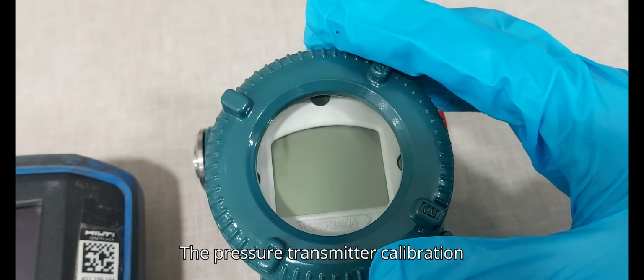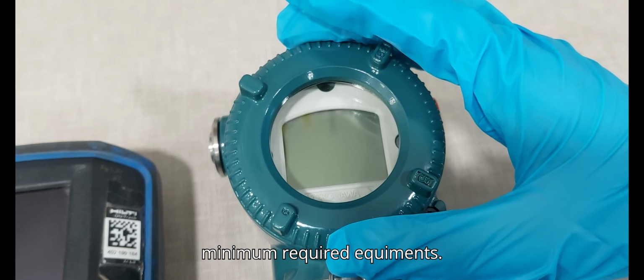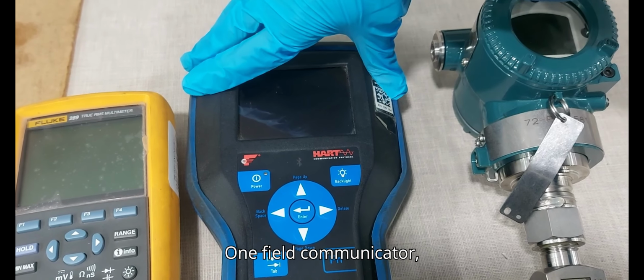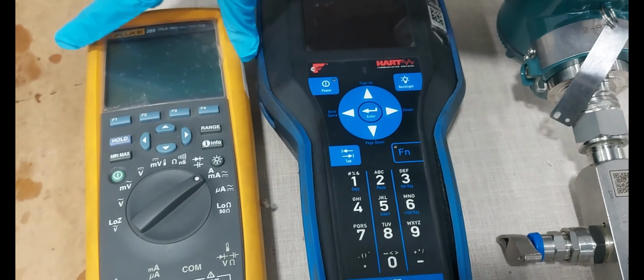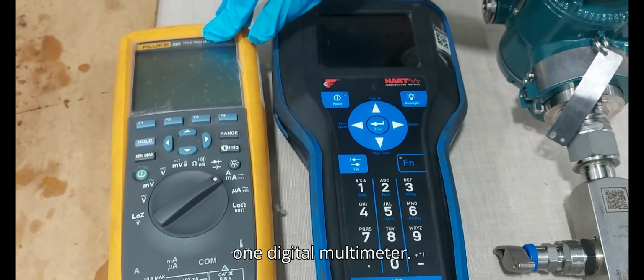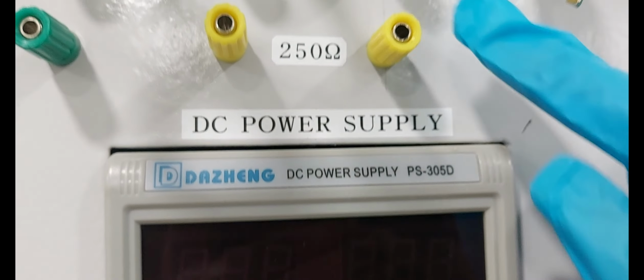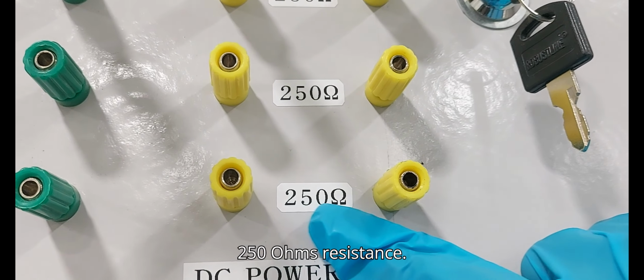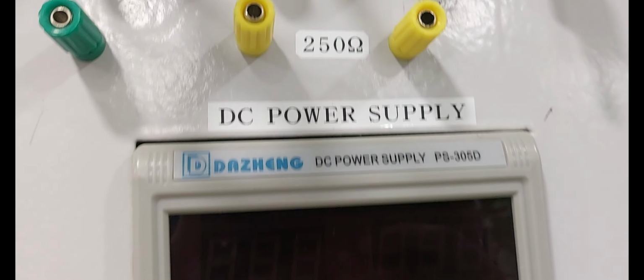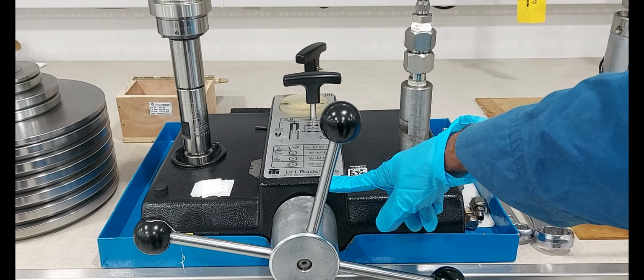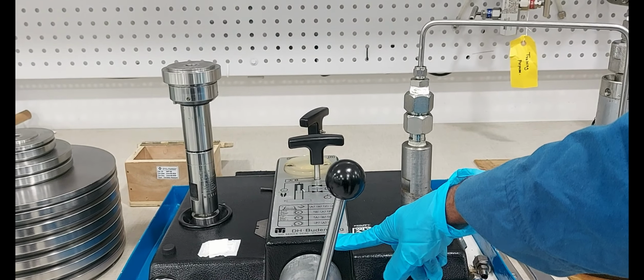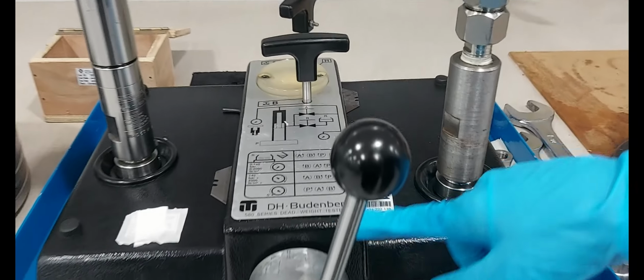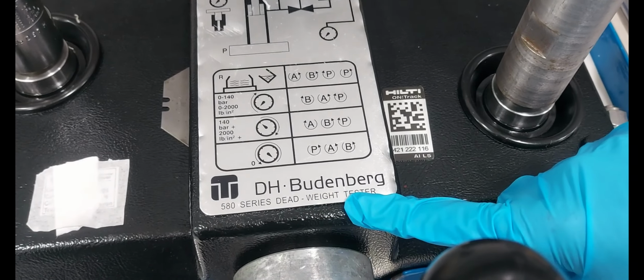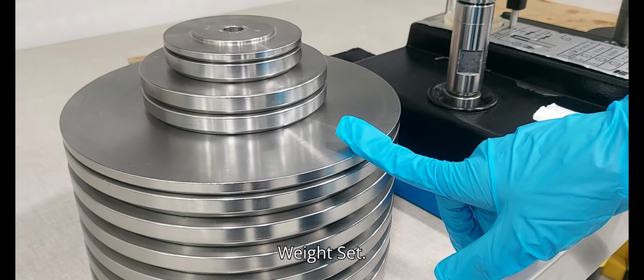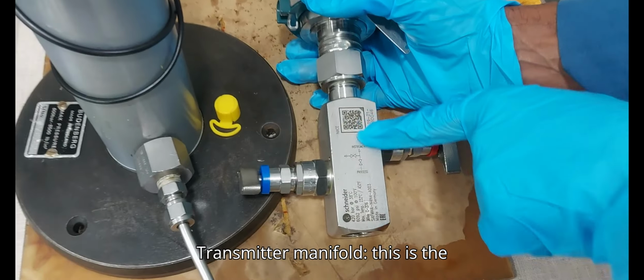The pressure transmitter calibration minimum required equipment: one field communicator, one digital multimeter, DC power supply, 250 ohm resistance, dead weight tester, pressure source, dead weight tester weight set, and transmitter manifold.